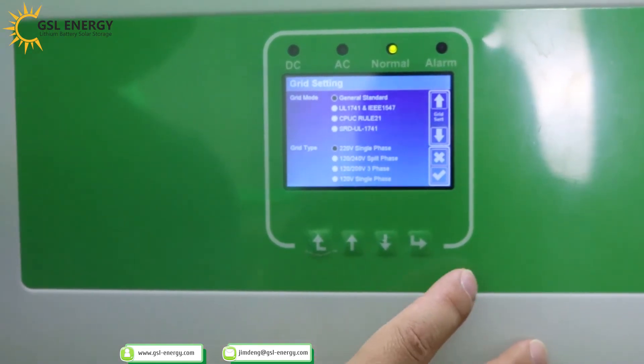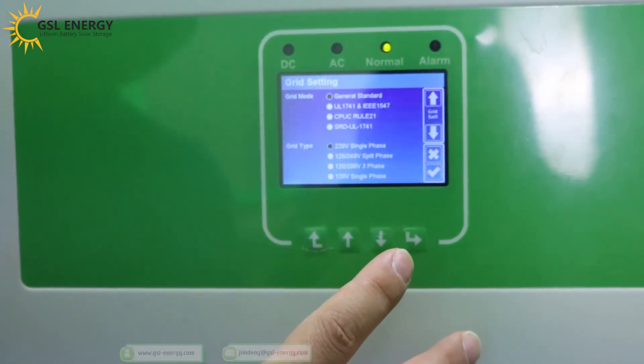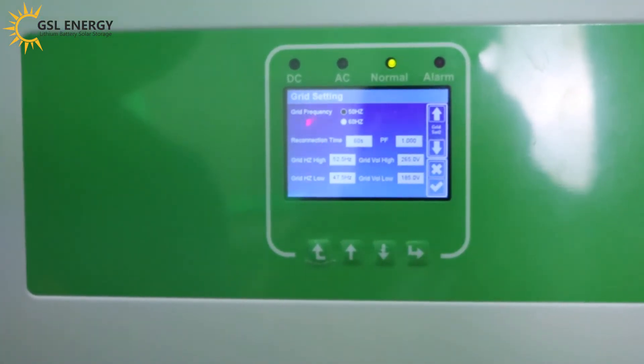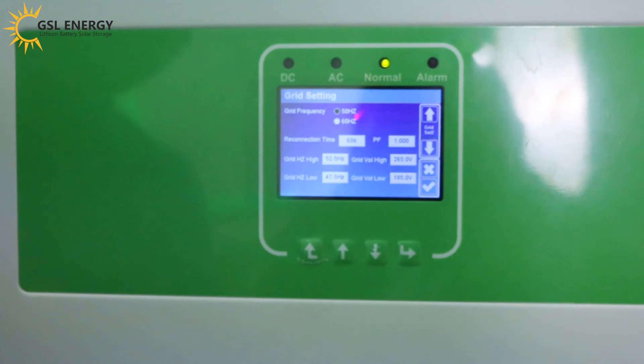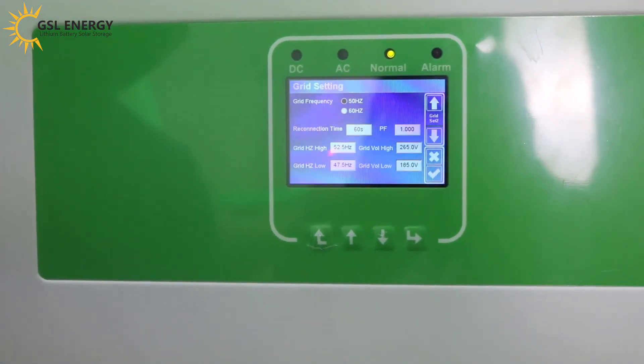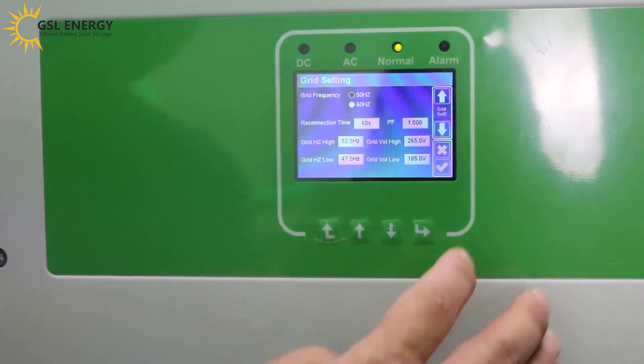Next is the grid setting. Choose your local grid mode and grid type. For single phase — currently in China, it's single phase. Frequency: 50Hz. Set the high and low voltage tolerance for grid protection.